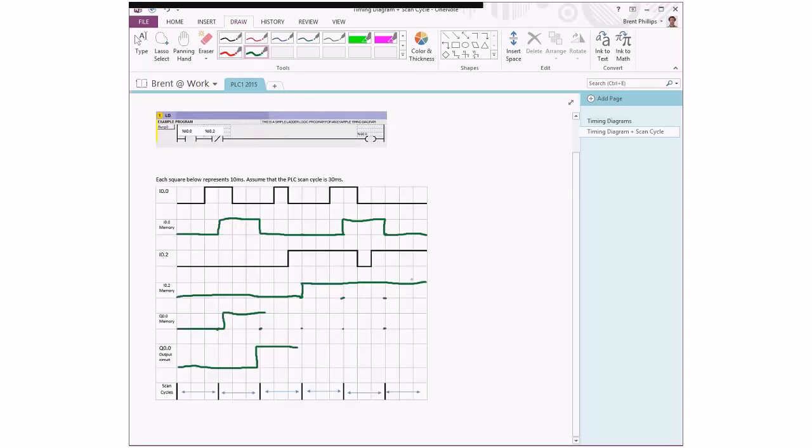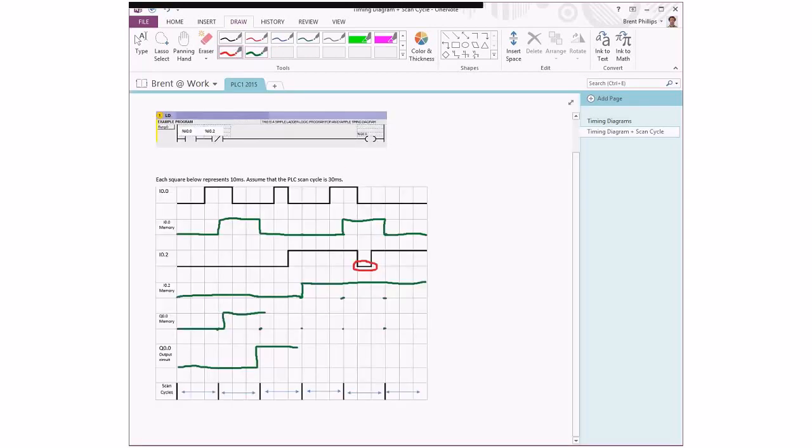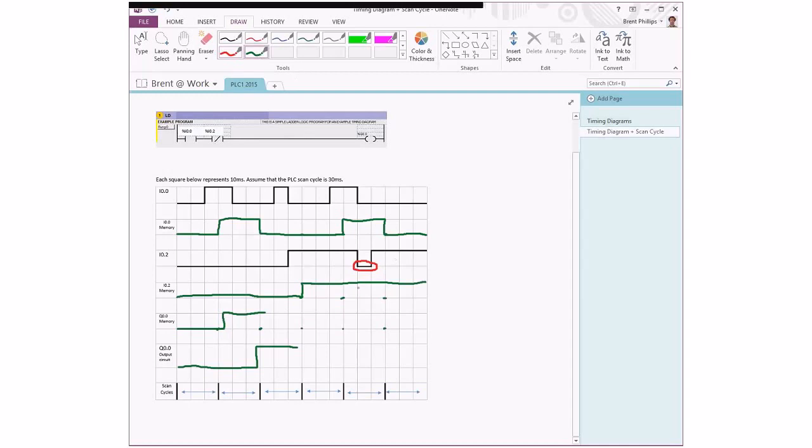So you'll notice that this little dip for I0.2, that one actually never shows up in the actual memory. So it's another issue where you get these short pulses, whether it's a pulse changing from low to high or high to low, the PLC can miss those. But it does mean that our PLC gets to execute the ladder logic based on some very stable states of the inputs.